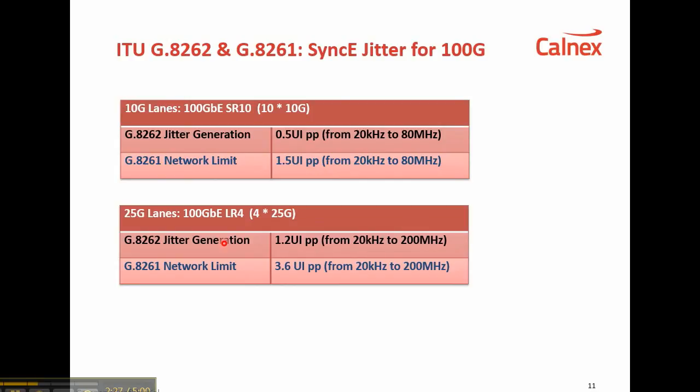A reminder that we are measuring to the G.8262 network equipment limit — that's the 1.2 UI peak-to-peak measurement shown here. There is also another limit, G.8261, which is the network limit at 3.6 UI peak-to-peak in the same measurement bandwidth. The measurement bandwidth of 20kHz to 200MHz is fixed within the Paragon 100G.